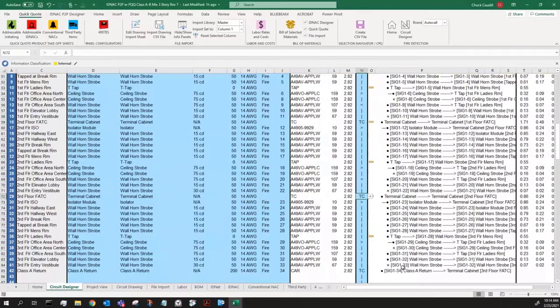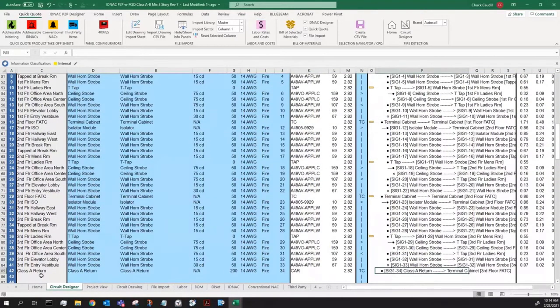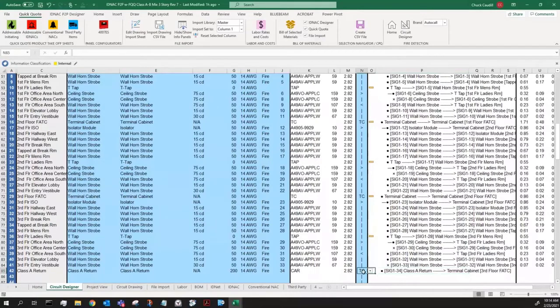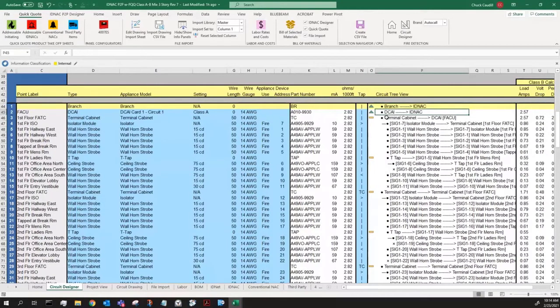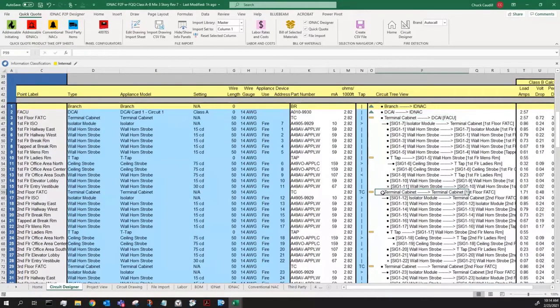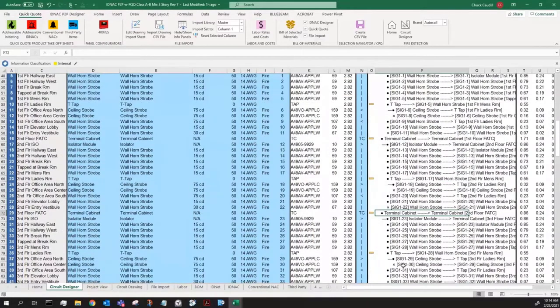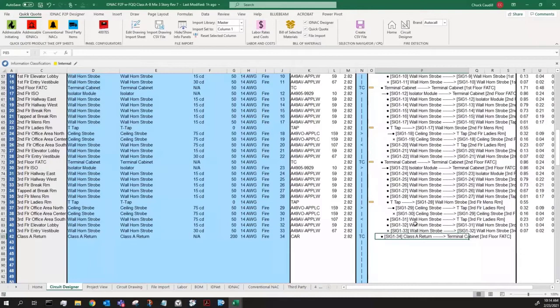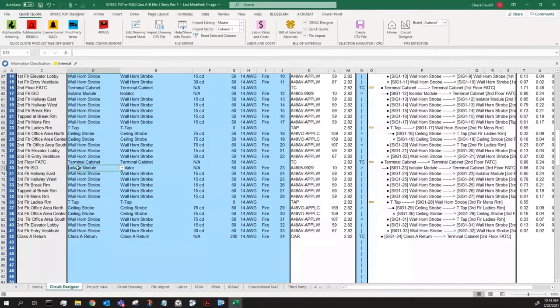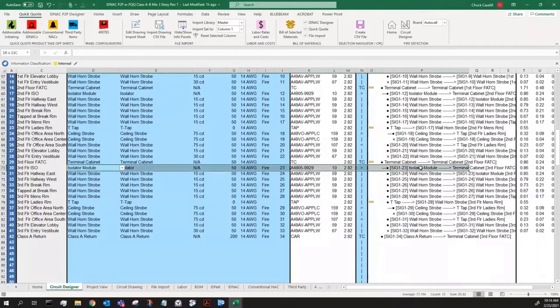And then finally, the Class A return, which is at the third floor at the end, it ties to this TC above it. So you can see these levels. The far left level is the Class A loop. This, this, this, this, this, this line, and the Class A return are all part of that Class A loop. The actual devices on the floors are tapped out through an isolator module in the very first thing with the right arrow to tap it.